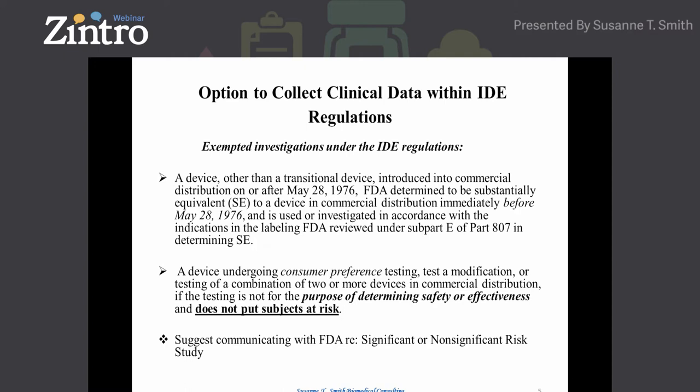FDA may at some point contact the sponsor or manufacturer and ask them to file a PMA, or the sponsor may want to down-classify to a Class 2. It's a very large project that takes time and can be expensive. But as long as your device has substantial equivalence and you have a pre-market approval or 510(k) on it, you can conduct a clinical trial providing it's within its indications for use labeling. Another exemption to be aware of is consumer preference testing.